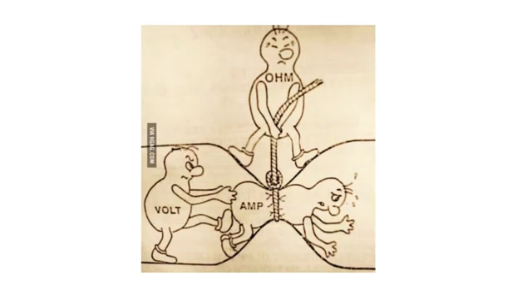So we can look at a chart, and the chart will say that a 15 amp circuit uses a number 14 gauge wire, and the actual size is about a 1/16 of an inch. And a 20 amp circuit requires a number 12 gauge wire. Remember, in metal, as we go lower in number, in gauge, we get thicker. And the actual size is a little bit bigger.